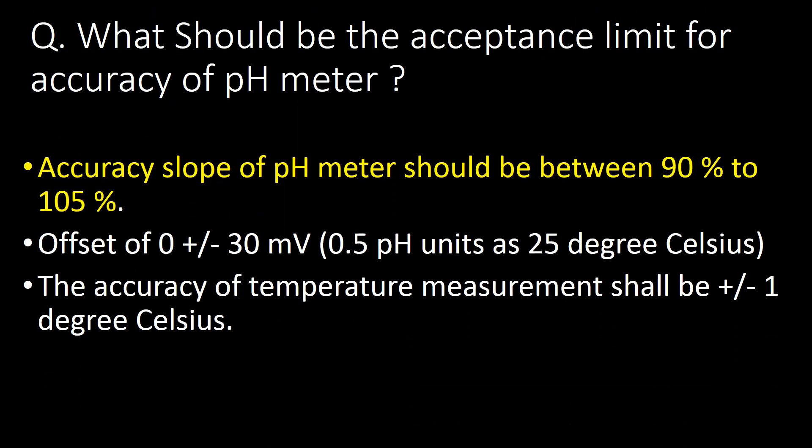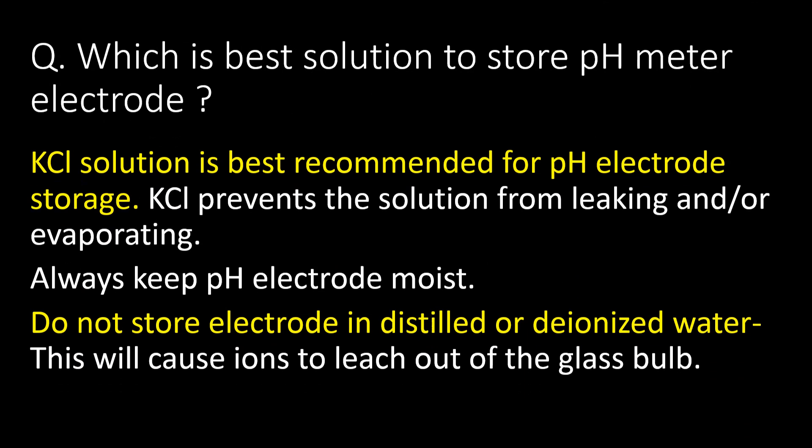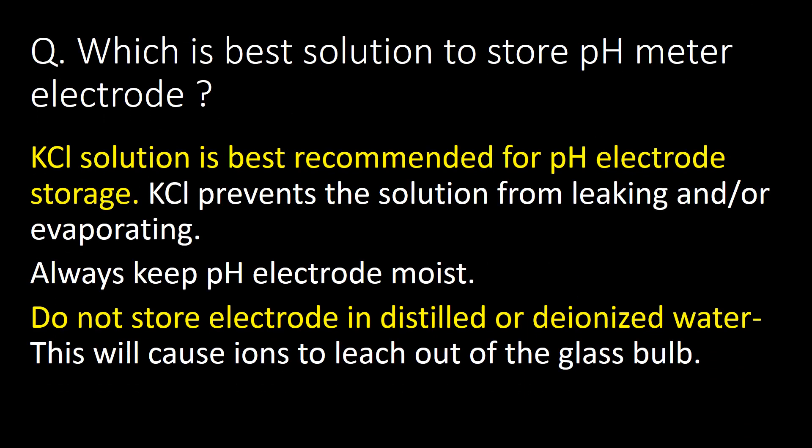What should be the acceptance limit for accuracy of a pH meter? The accuracy slope of a pH meter should be between 90% to 105%. The offset should be zero plus or minus 30 millivolts, and the accuracy of temperature measurement shall be plus or minus 1 degree Celsius.